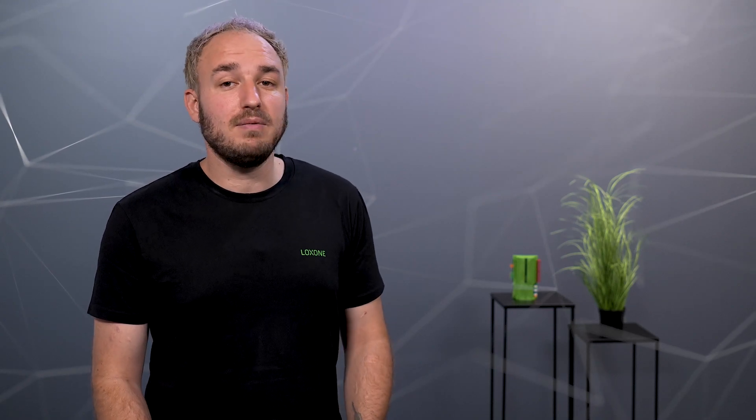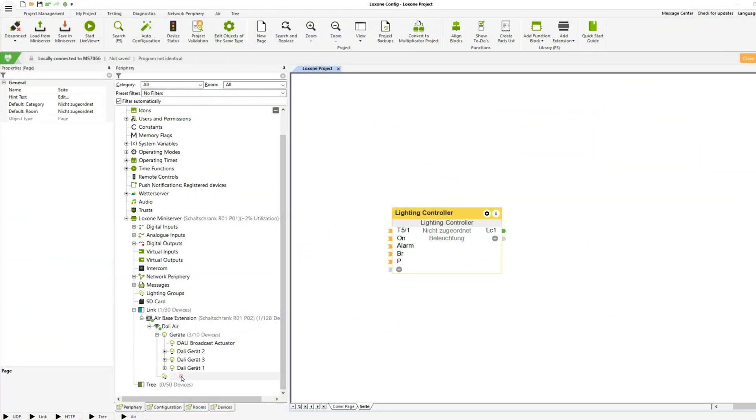If several DALI lights are to be controlled simultaneously, a DALI group is recommended. This has the advantage that the programming becomes clearer and there is no time delay when dimming the lights. When teaching the DALI devices, existing group assignments are loaded and created in Loxone config.